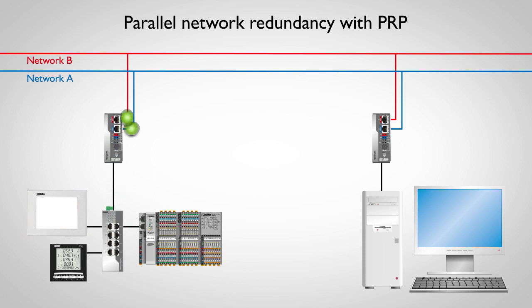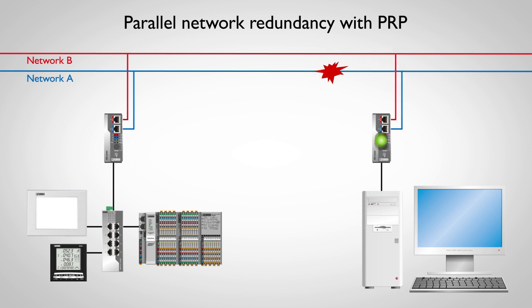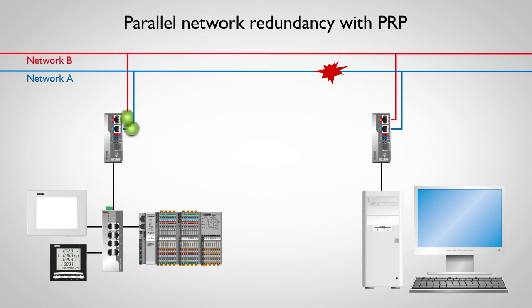The data package received first of all is used at the target device. In the event of a disturbance or interruption in a network, the data package reaches the recipient via the second network, without any delays caused by switchover time or reconfiguration time. Data traffic continues to run without interruption, thanks to bumpless redundancy.